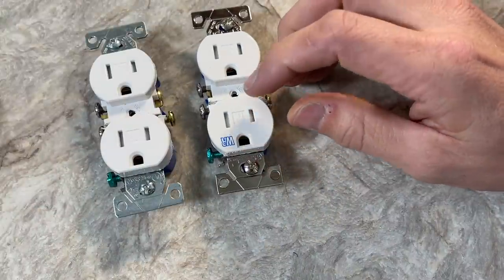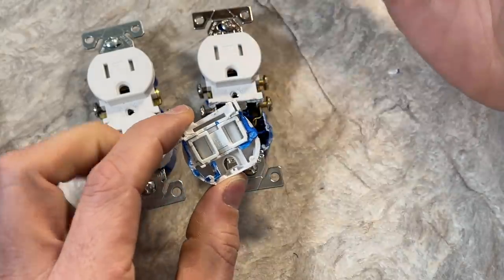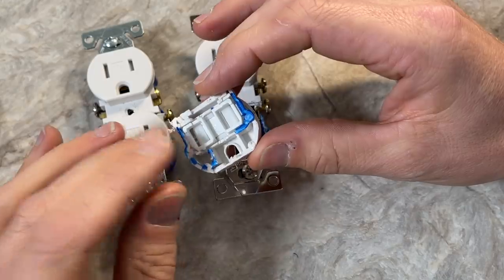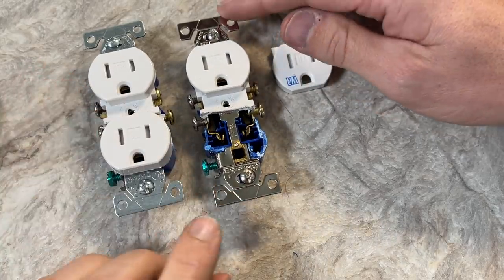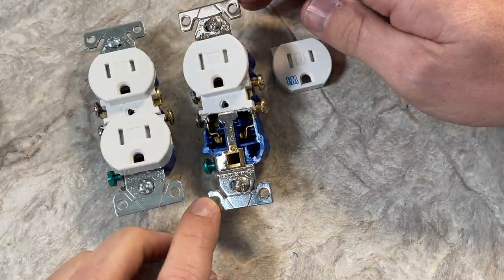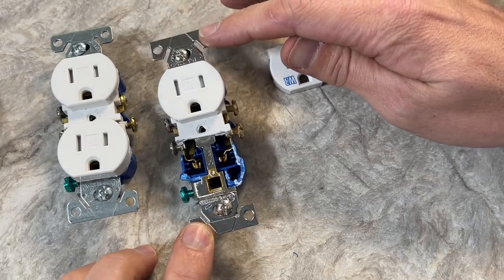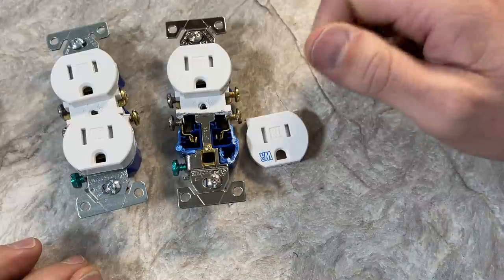There is also a tamper and weather-resistant outlet. To be honest, I was thinking there was going to be additional sealing within the plug itself — that if these are put in wet or damp areas, moisture couldn't get into the actual outlet or receptacle. I was wrong. It's still the same tamper-resistant shutter design, exactly the same. The only difference I see is the bracket itself and the mounting screws, which are stainless steel so they're more resistant to corrosion. That really drives about three additional dollars — so $1 for the standard tamper-resistant, $4 for the tamper and weather-resistant. You're paying a premium for the stainless steel feature.